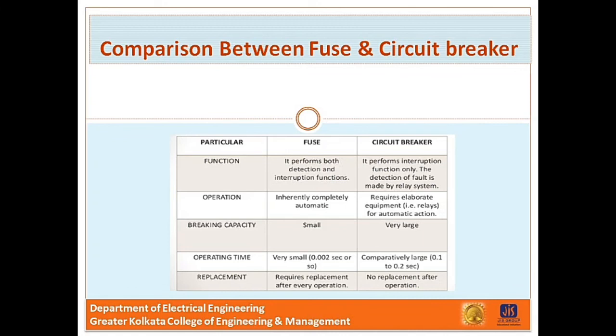Now, some types of circuit breakers must be maintained on a regular basis to ensure their mechanical operation during an interruption. And this is not the case with a fuse, which is based on melting processes where no mechanical operation is required for the fuse to operate under fault. Now, in a multi-phase power circuit, if only one fuse opens, the remaining phases will have higher than normal currents and unbalanced voltages with possible damage to motors.